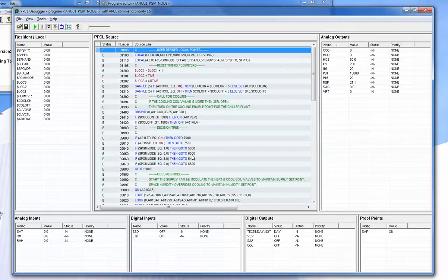Also, some PPCL commands don't do anything. For example, statements that require actual hardware and feedback from the firmware on the hardware. So for example, node 0 through 99 status, battery status, and such. Other examples are simply certain PPCL statements don't run. For those statements that actually require online operation, those statements have been, in essence, nulled out, and the statement executes, but the statement itself actually doesn't do anything, and the program continues.